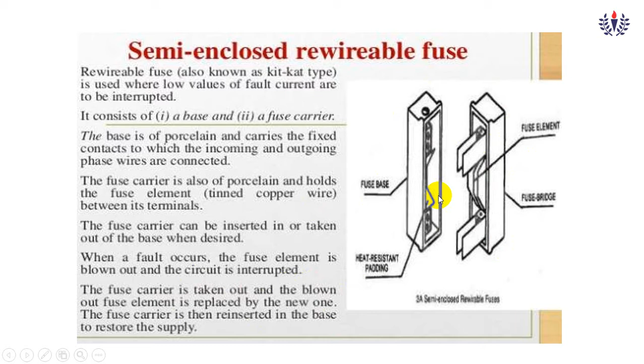When a fault occurs, the fuse element is blown out. Here you can see this connection will break so that the circuit is interrupted, because here it is the input, here it is the output. The fuse carrier is taken out and the blown fuse element is rewired. We can remove this wire and once again it can be rewired and you can use it to restore the supply. This is the common type which may be used in houses or some industries also. But the previous one we saw is the cartridge fuse. That is a use and throw type.